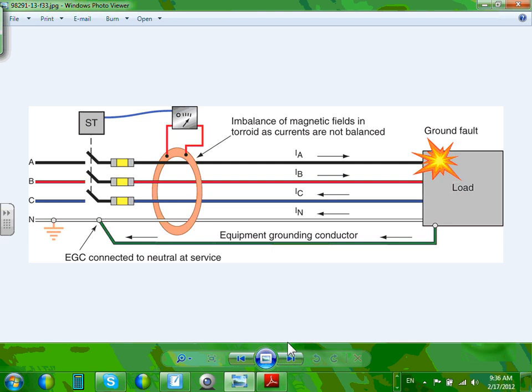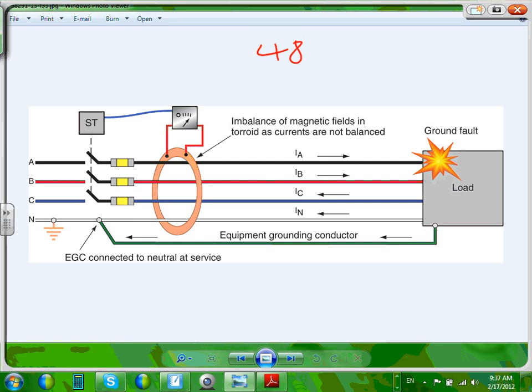If you have ground fault protection, guys, what they do in higher voltages, they have to put ground fault protection for equipment 1,000 amp or higher. So that's a means of providing ground fault protection for equipment. I want to just say one little thing about this one because we're coming to it. This is required for any system 480/277 volt and 1,000 amp or higher.